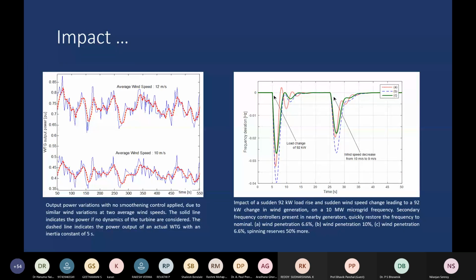So here we have the dotted curve on the left, the red dotted curve shows the active power variations because of wind speed variations. The wind speed variations are shown in blue. And the same changes applied at 10 meters per second and at 12 meters per second are shown below. And you can see that the same change applied at 10 meters per second causes a much lower change in the power output compared to if you apply the same change at 12 meters per second, where the power output changes much faster.